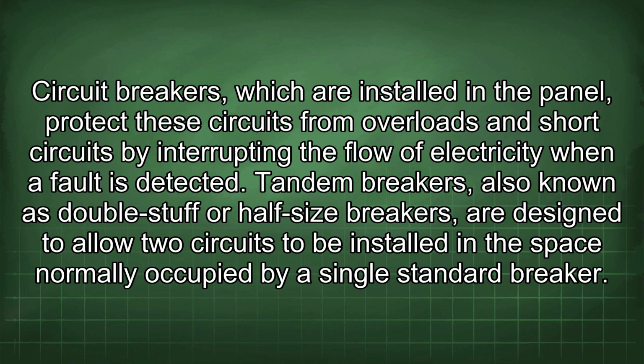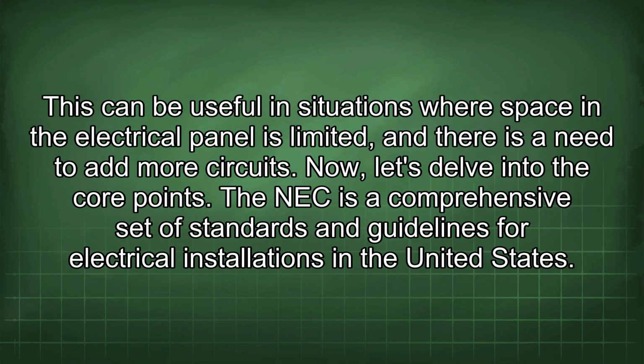Tandem breakers, also known as double stuff or half-size breakers, are designed to allow two circuits to be installed in the space normally occupied by a single standard breaker. This can be useful in situations where space in the electrical panel is limited, and there is a need to add more circuits. Now let's delve into the core points.